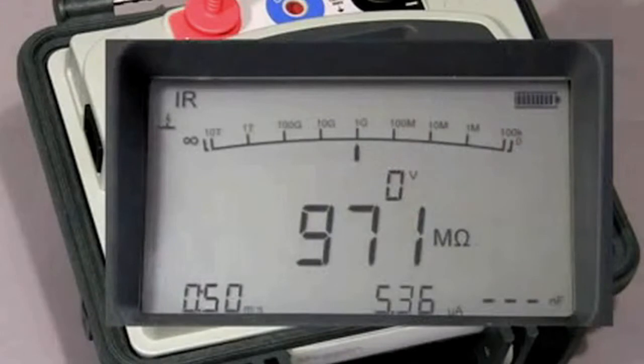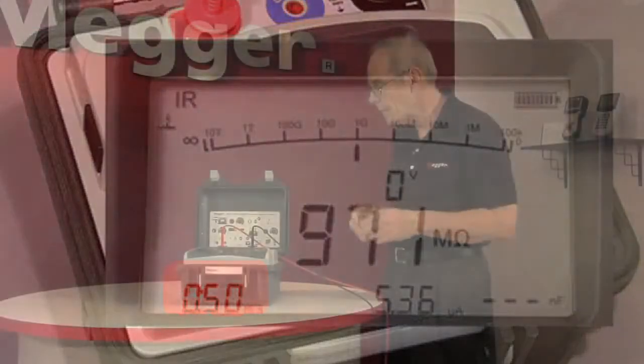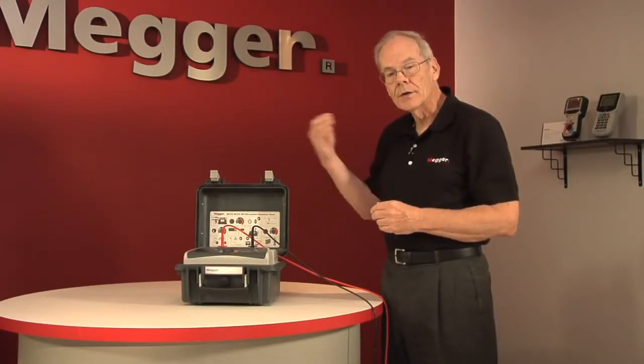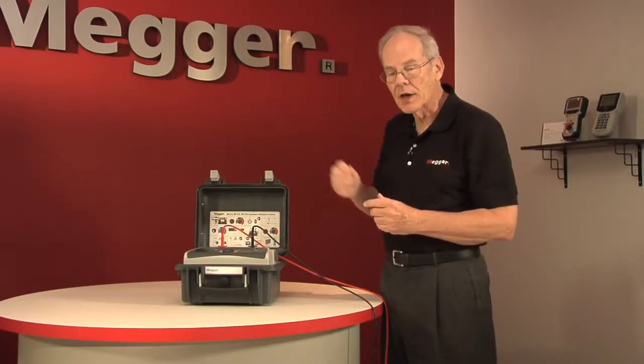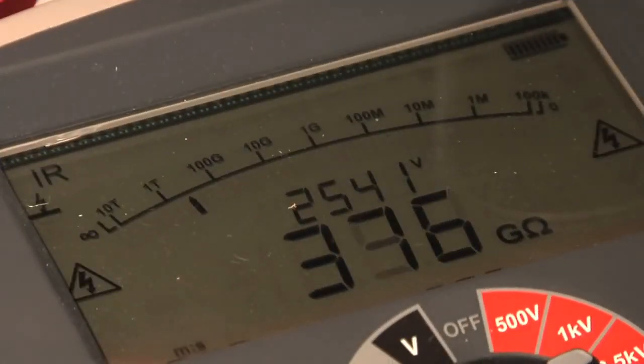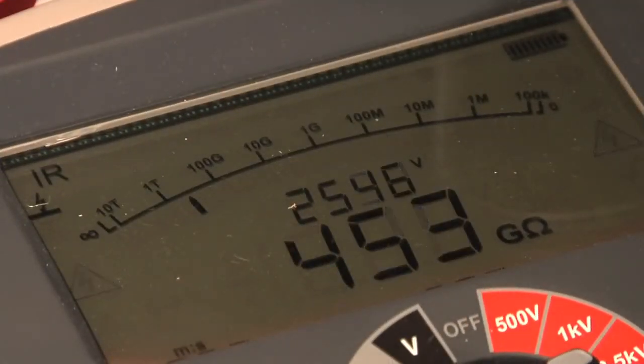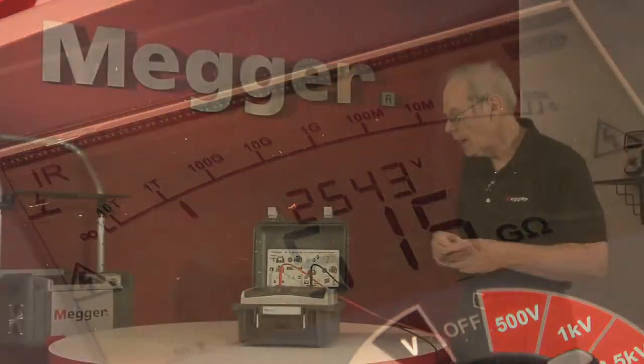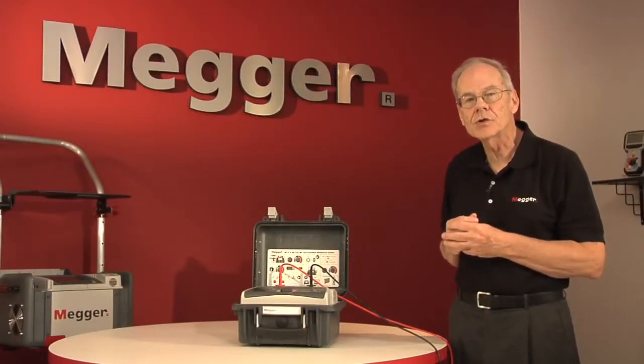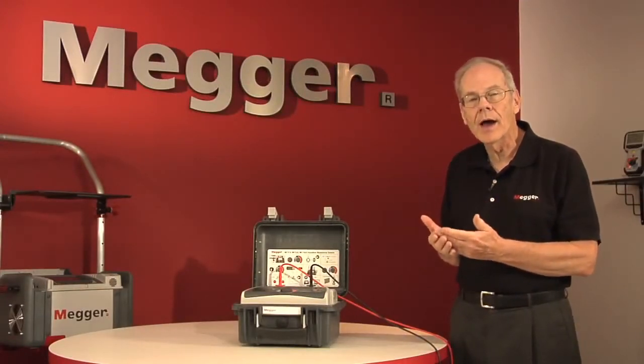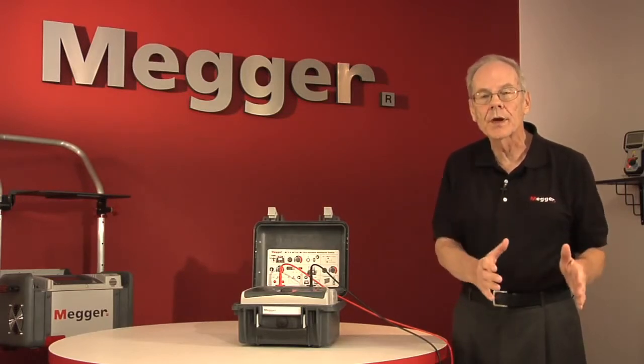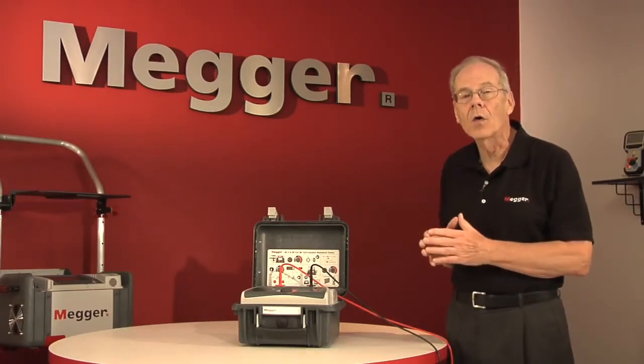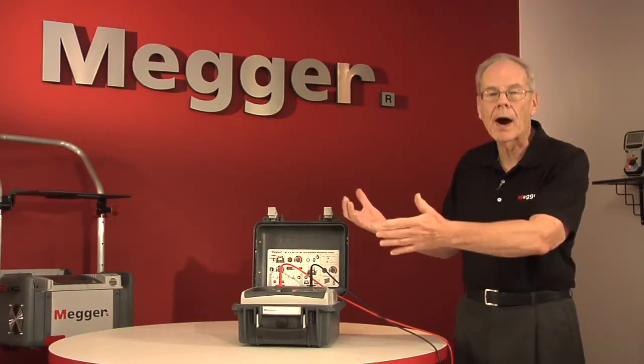Insulation resistance tests are highly dependent upon time, and a convenient timer on the display keeps you apprised of that at all times. Initially, you will get readings that are constantly rising because the test item is charging, and so it's pulling charging current, primarily capacitance, and as it does so, the resistance will climb. At some point when the test item becomes fully charged, the readings will stabilize, and that is the final resistance reading of the test item. That's the goal of the insulation resistance spot reading test.